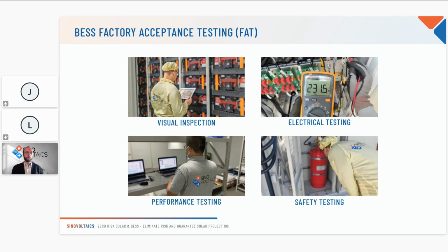Last but not least, safety testing - making sure the fire suppression system and smoke detector are working well. For your information, the single most common defect we see during FATs: in about 25% of the projects we inspect, we have at least one container with a fire safety system not working, which is a bit scary if you ask me.